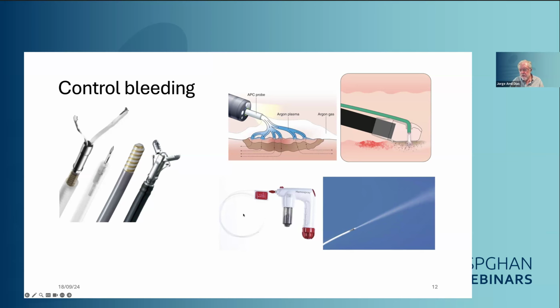There are some specific notes about using this particular hemospray, is that any drop of water inside the tubing will coagulate the product, and this tube will be to waste. Therefore, this is applied inside the scope without connecting to this device. Then a few syringes of air are pushed down the tube in order to remove any remaining drop of water that may have been collected while traveling inside the channel of the scope. And only after that, you apply it here, you open the valve, you open there a canister, there's a small metal canister with a pressure gas in here that is opened by twisting this, and then pressing this button deploys the powder onto the mucosa.